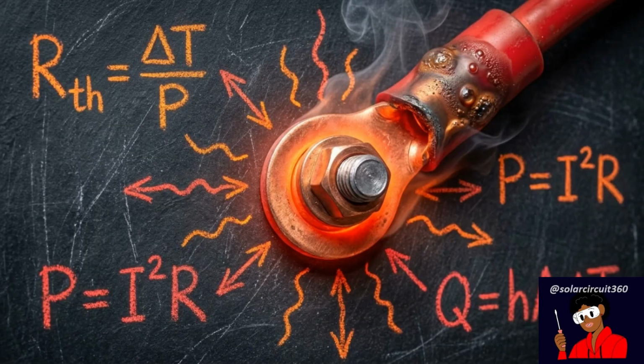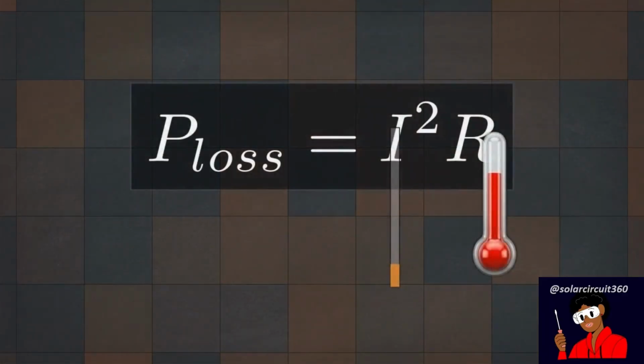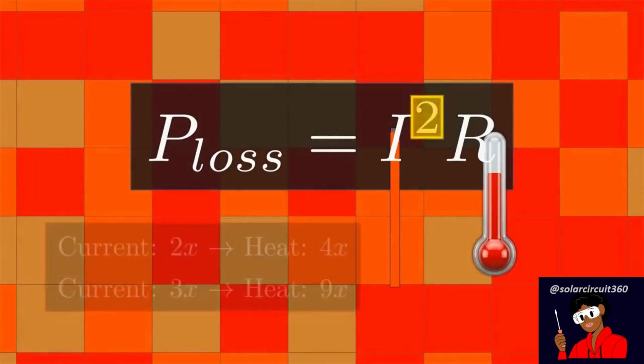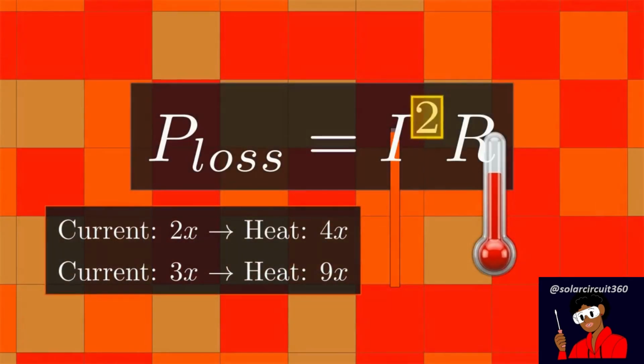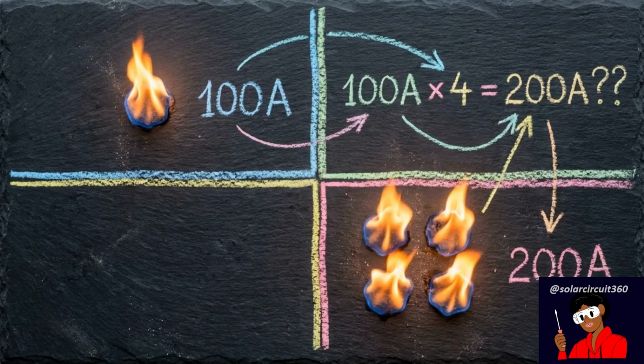Beyond physical copper mass, large off-grid solar arrays face an invisible threat: resistive heat generation. Look at this thermal heat map overlaid with Joule's law of heating. This equation governs exactly how much energy is wasted as heat inside your cables. The critical detail here is the exponent. The current variable is squared. Heat does not scale linearly with amperage. Because of that square, if your continuous current doubles, the physical heat generated inside your wiring increases by a factor of 4.